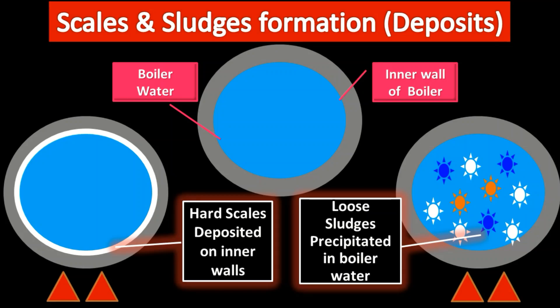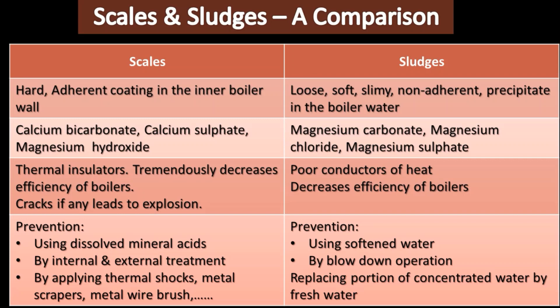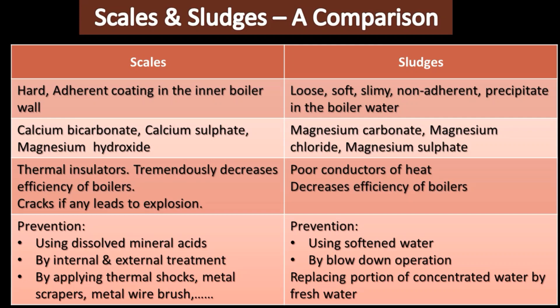Comparing scales and sludges: scales are hard, adherent coatings on the inner boiler wall, whereas sludges are loose, soft, slimy, non-adherent coatings in the boiler water. Calcium salts usually cause scales and magnesium salts cause sludges. Scales are thermal insulators — they tremendously decrease the efficiency of boilers. Even if we supply continuous heat, the scales will not allow heat to pass through to the water, so it takes a lot of time to make the water boil. Sludges are also poor conductors of heat and decrease efficiency, but not as severely as scales.